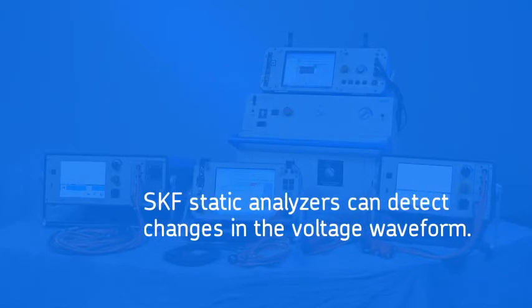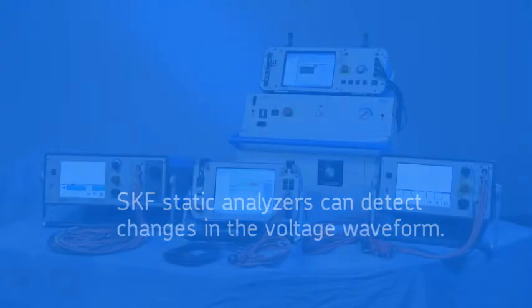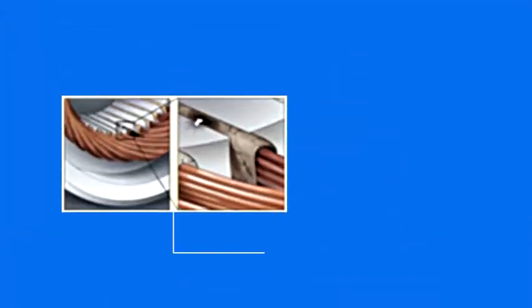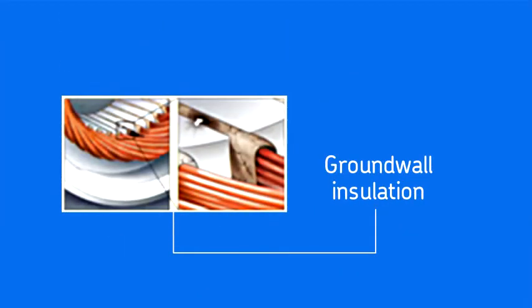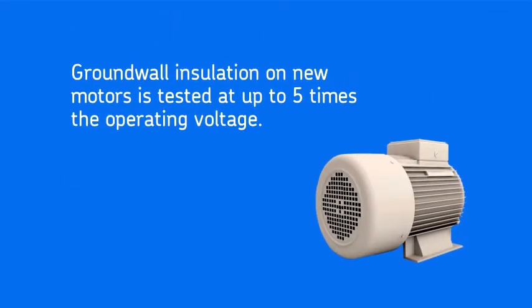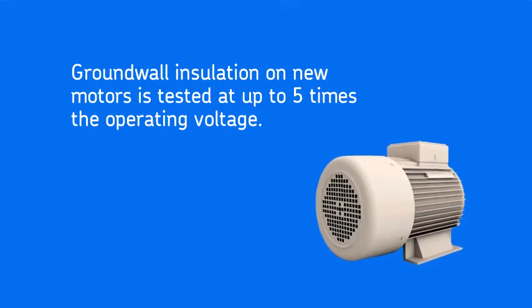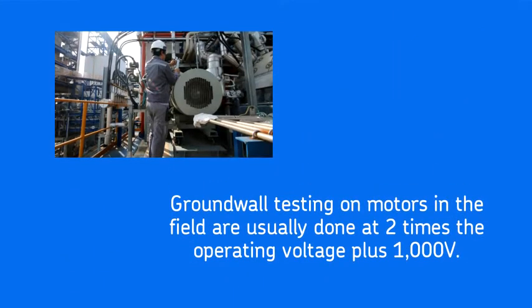The ground wall insulation is the insulation between the stator windings and the stator core. When the motor is new, this ground wall insulation is tested at voltages up to five times the operating voltage. For motors in the field, ground wall testing is usually done at two times operating voltage plus 1000 volts.